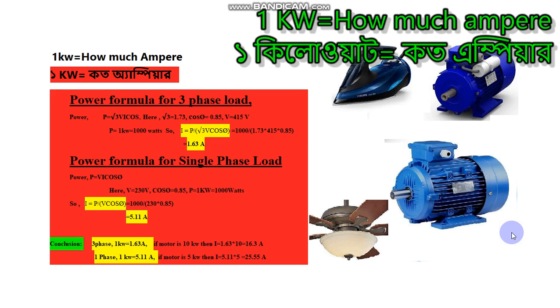Now let's talk about the single-phase load calculation. The power formula for a single-phase motor is P = V × I × cosθ. Here, V = 230 volts and cosθ = 0.85. For a load of P = 1 kilowatt (1000 watts), rearranging gives I = P ÷ (V × cosθ) = 1000 ÷ (230 × 0.85).